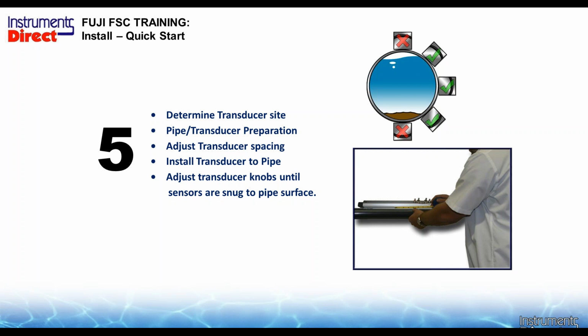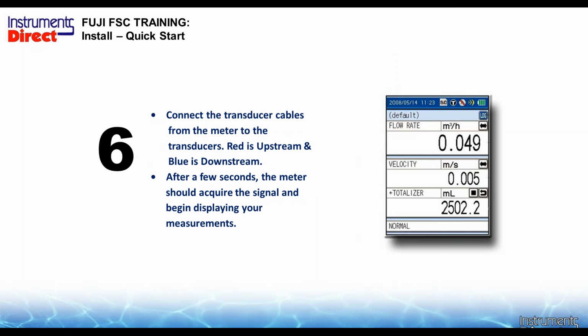And if your transducer has adjustable knobs on them, in addition to going right and left, they go up and down. Nothing worse than getting a phone call and the guy can't get a reading, and all he has to do is tweak a couple of twist knobs there to push the transducer down so it's kissing the pipe. It needs to have a snug surface or mechanical contact of the actual transducer sensor to the pipe wall itself. Not the rail so much, it's the sensor. The rail's just there to help you make a measurement and make life a little easier.